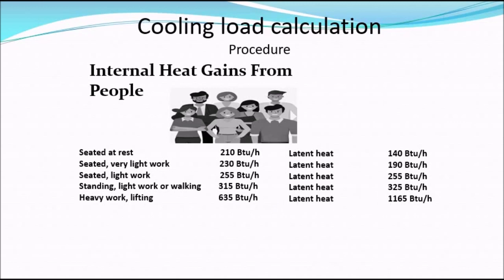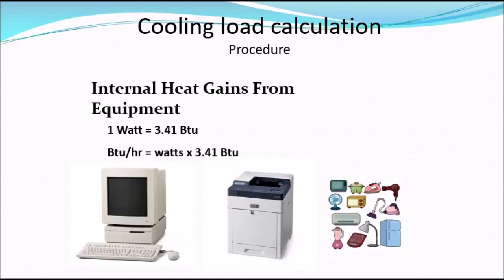The next thing to consider is internal heat gains from equipment and appliances such as computers, printers, irons, ovens, and everything that can generate heat within the building. Basically, one watt is equal to 3.41 BTU/hr, and BTU per hour equals watts multiplied by 3.41. There are many types of appliances and equipment in restaurants, schools, office buildings, and hospitals that may generate significant heat to be accounted for in the cooling load.